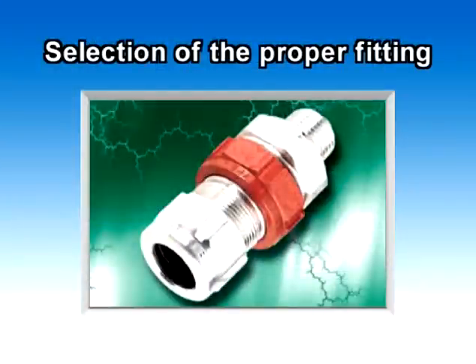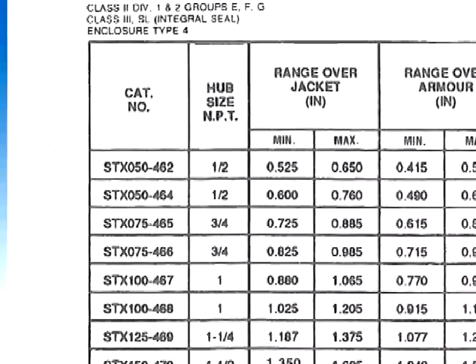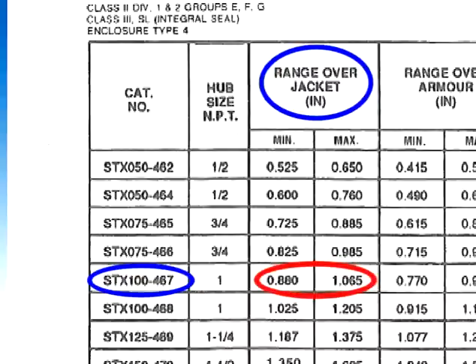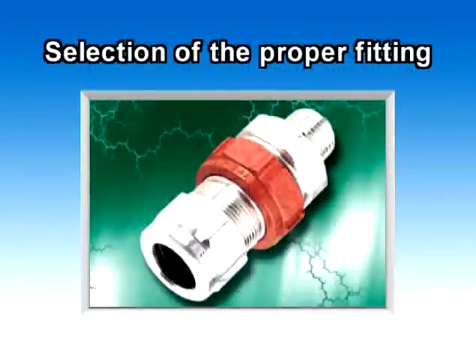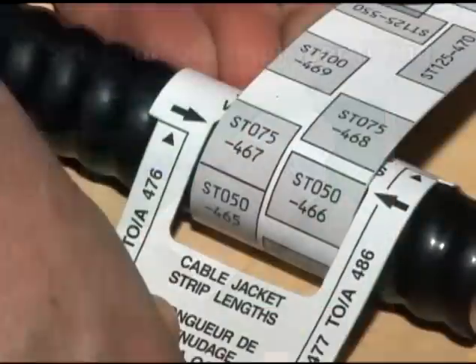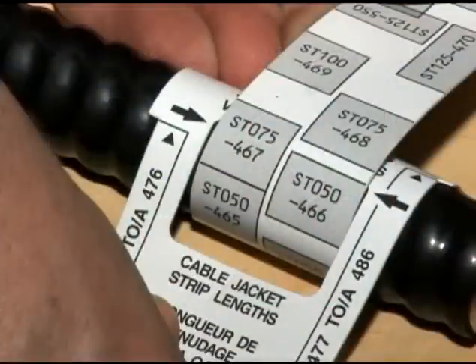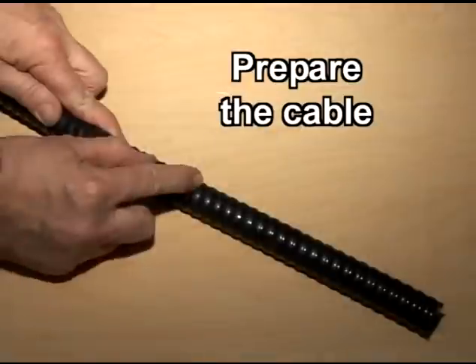To select the proper Star Teck XP fitting, you must know the outside diameter of the cable, including its outer jacket. With this information, refer to the instruction sheet supplied with the fitting. You can also refer to the cable range engraved on the Star Teck XP's gland nut to match the correct fitting with the cable. Thomas & Betts also offers a Star Teck Wraparound Ruler, available through your local distributor, to help you select the proper fitting if you do not know the cable diameter on hand.